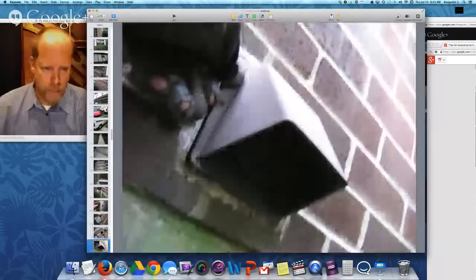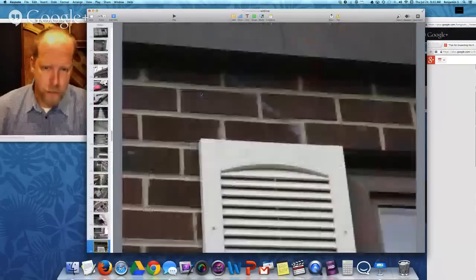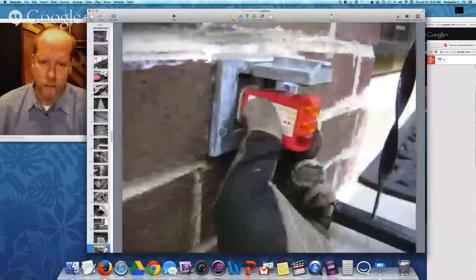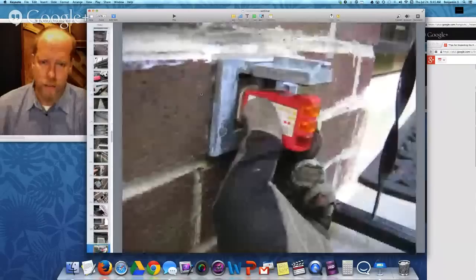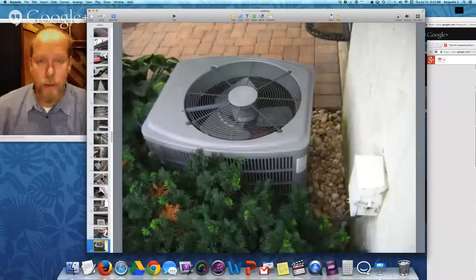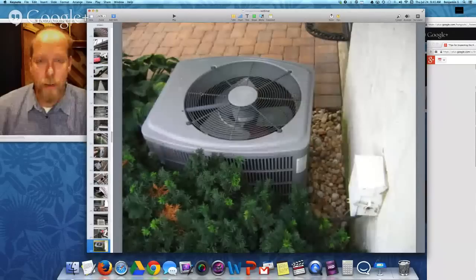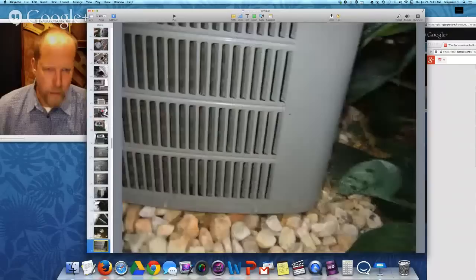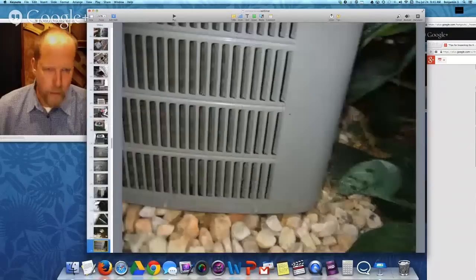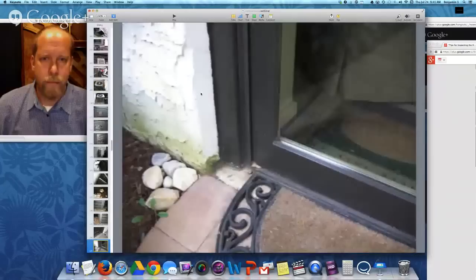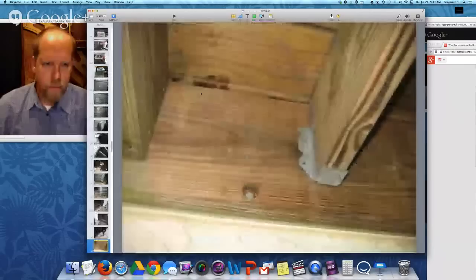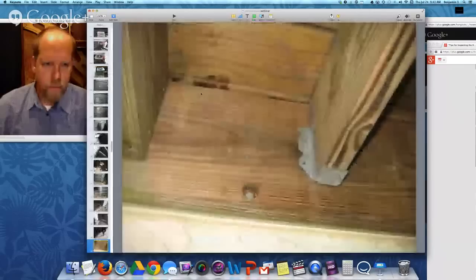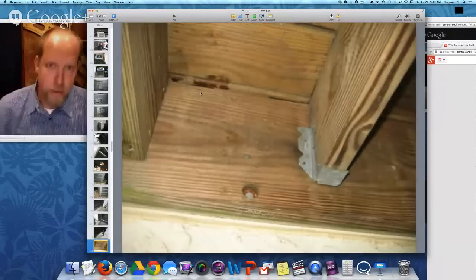I follow every hole I see in the exterior — I'll remember it and find it on the other side. There's the dryer vent exhaust too. There's a crack patched with sealant. I test all exterior receptacles, making sure they're GFCI protected. There's the air conditioner on the outside — another system interdependent with the exterior system. The condensate discharge pipe should be discharging far away from the house — this one is not. When I take a look at any door or window, I tend to look at the four corners: top left, top right, bottom left, bottom right. Here at the deck again, I want to go back and take a closer look.